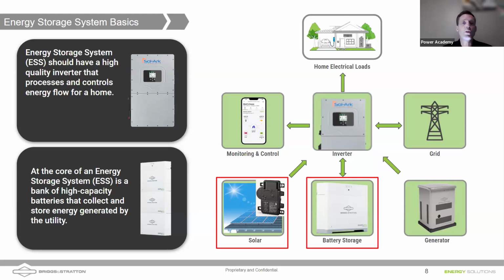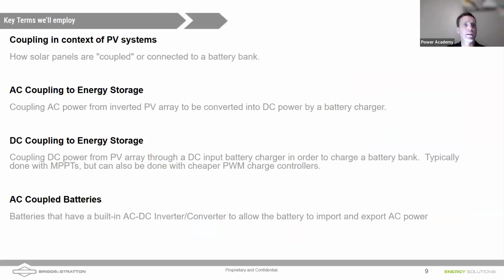With AC coupling, what we're really looking at is the connection between the AC solar and the battery, right? You could have a system on your roof where the solar panels are connected together in a string and running into an existing inverter on the home, or those panels are connected to microinverters, and those microinverters are feeding AC back into the load center of the house. So when we're talking about AC coupling, we're talking about the relationship between the inverter that's connected to the solar and the batteries. Some key terms here: coupling in the context of PV systems. What we're talking about is how the solar panels are coupled to the battery bank. When we refer to AC coupling to energy storage, what Daniel and I will mean in this talk is coupling AC power from an inverted PV array that's going to be converted to DC power by a battery charger.